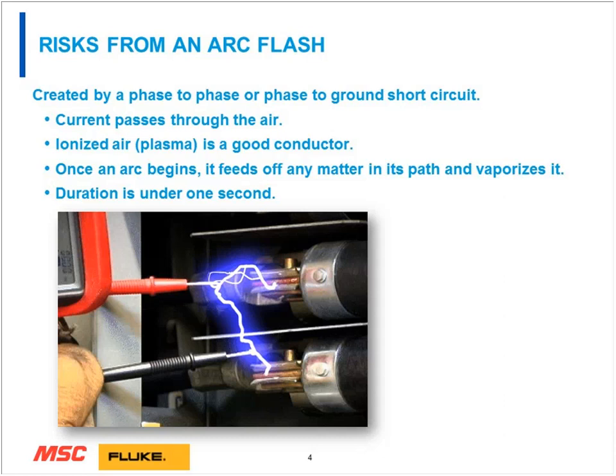So as you pull away from the contact point, that arc continues to grow, and if the arc crosses itself at any point, that's where the danger occurs, because that becomes that phase-to-phase connection. So there's a lot of danger in making the connection, and if an arc starts, obviously it can jump across the two different phase connections.